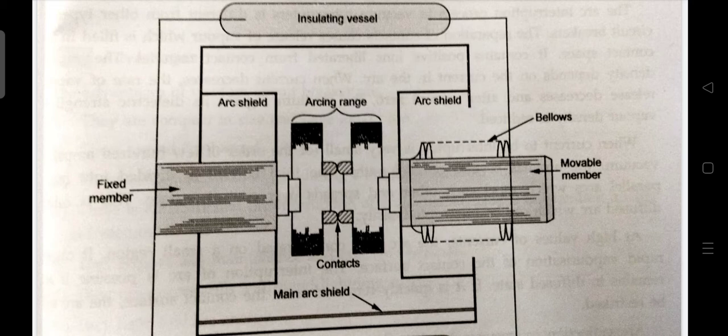Since vacuum has very fast rate of recovery of dielectric strength, the arc extinction in a vacuum breaker occurs with short contact separations like 0.625 cm. It has so many advantages like they are compact, reliable and have longer life. There are no fire hazards. They have low arc energy. They can successfully withstand lightning surges. There is no generation of gas during and after operation. They require very little maintenance and are quiet in operation. They can interrupt any fault current. They have low inertia and hence require small power for control mechanism.